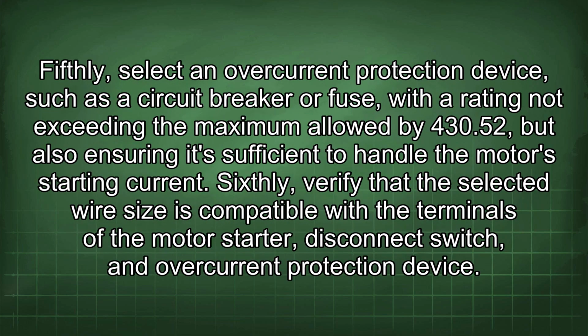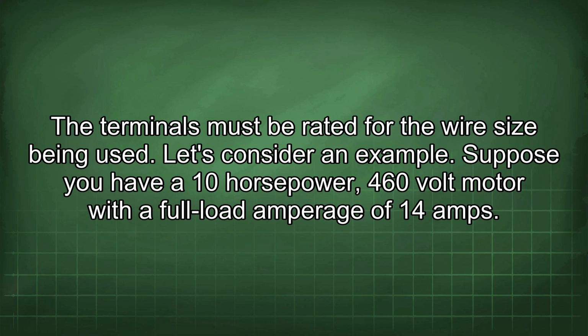Fifthly, select an overcurrent protection device, such as a circuit breaker or fuse, with a rating not exceeding the maximum allowed by 430.52, but also ensuring it's sufficient to handle the motor's starting current. Sixthly, verify that the selected wire size is compatible with the terminals of the motor starter, disconnect switch, and overcurrent protection device. The terminals must be rated for the wire size being used.